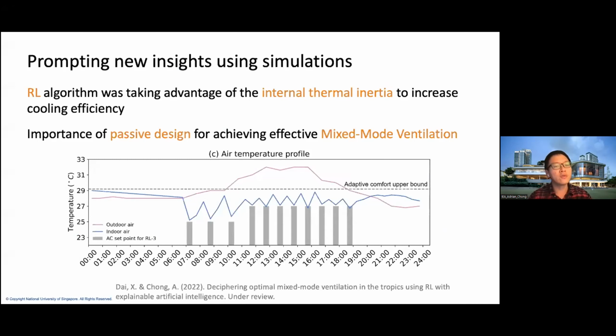As you can see, the windows were opening and closing. It cools to 24 degrees Celsius when it's not too hot outside, then opens with a smaller window opening to take advantage of the thermal inertia and smaller load, so it can operate in natural ventilation longer. Then it closes and cools again. When it's really hot, it opens for a shorter period since the outside load is much higher.